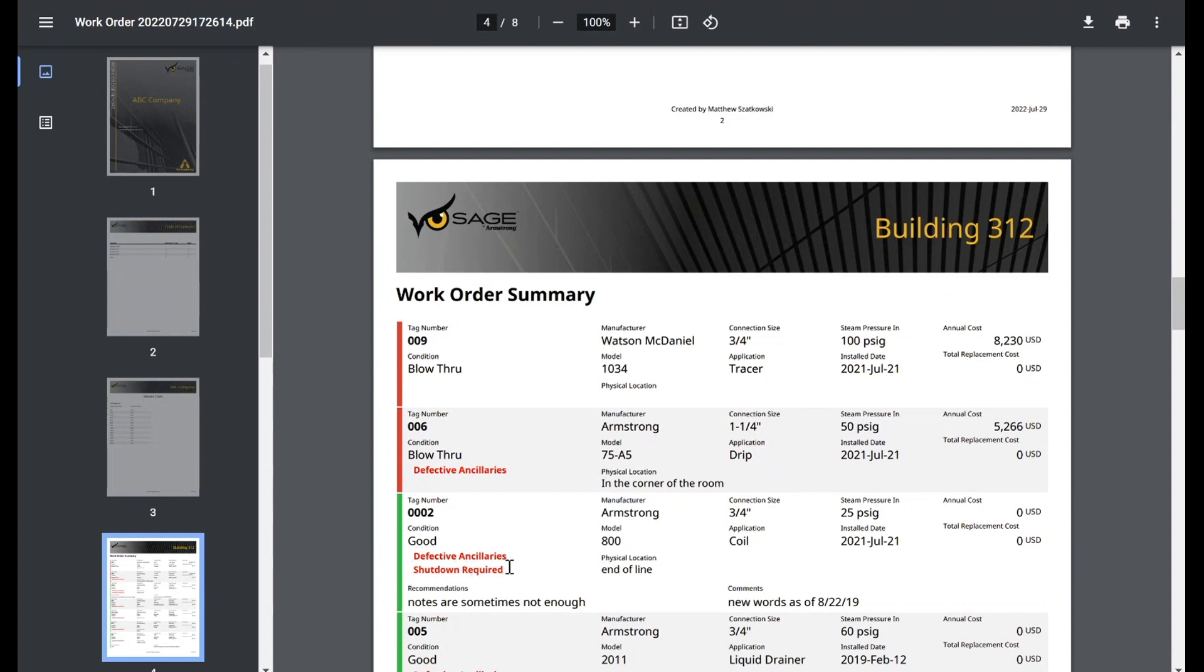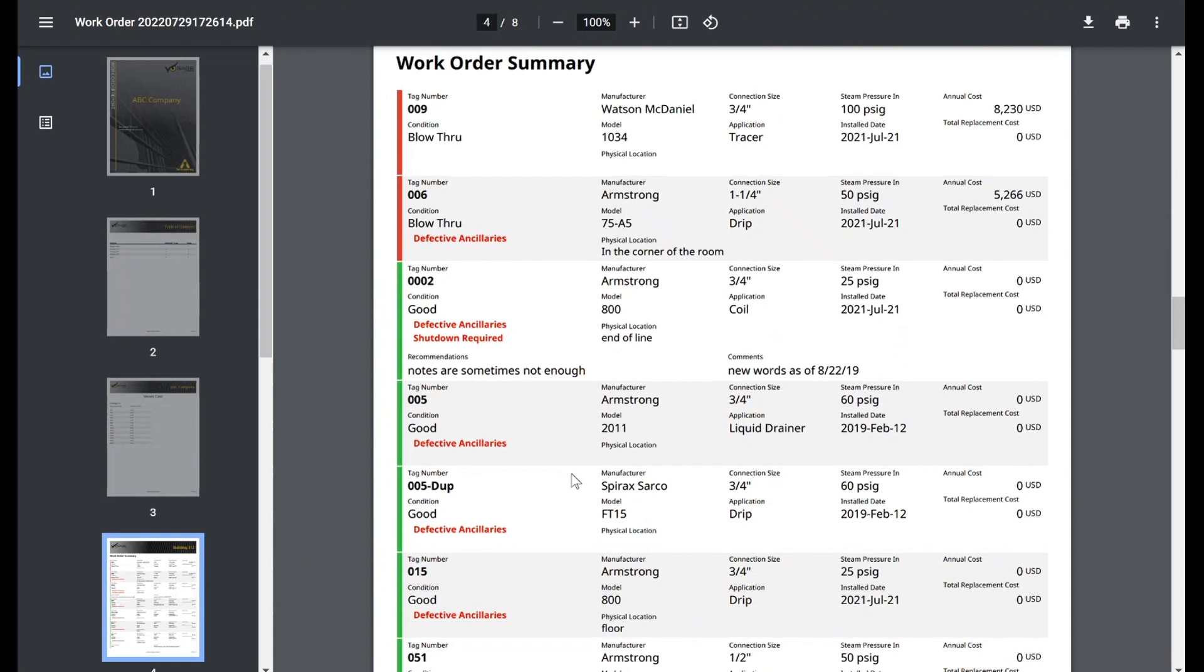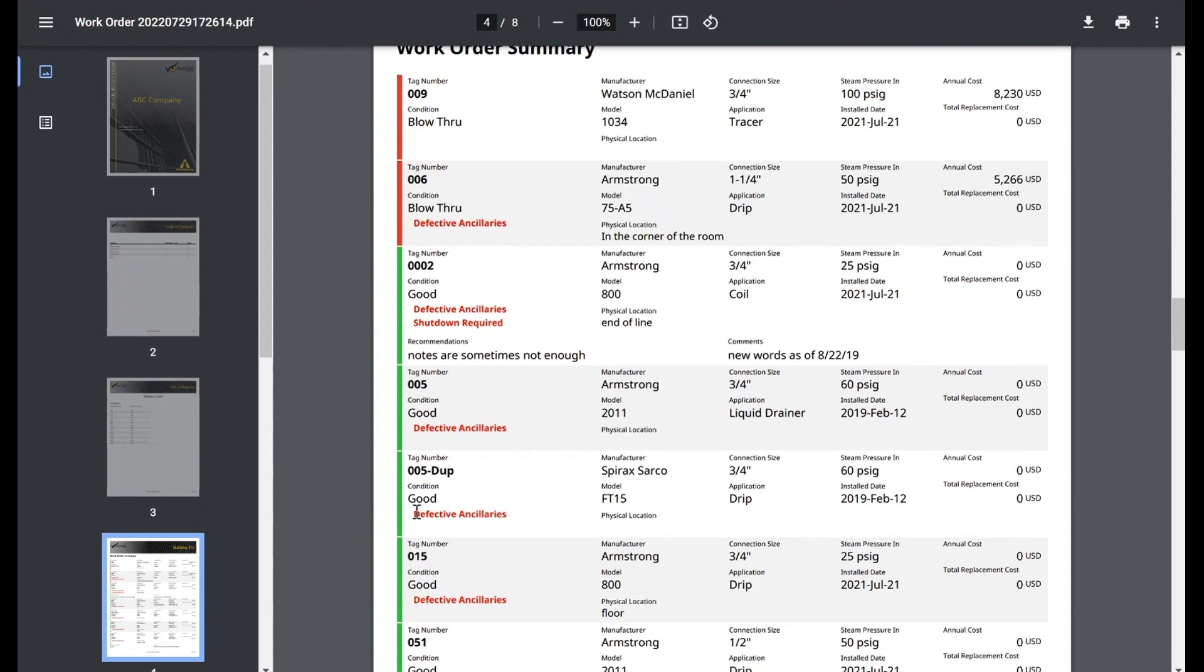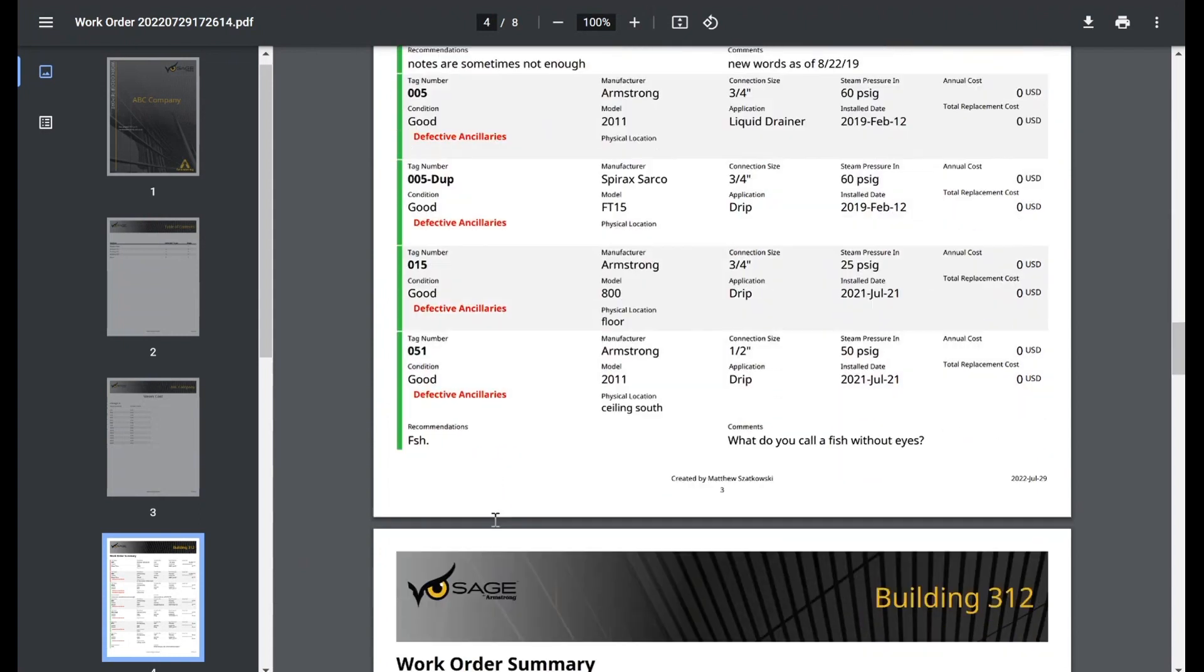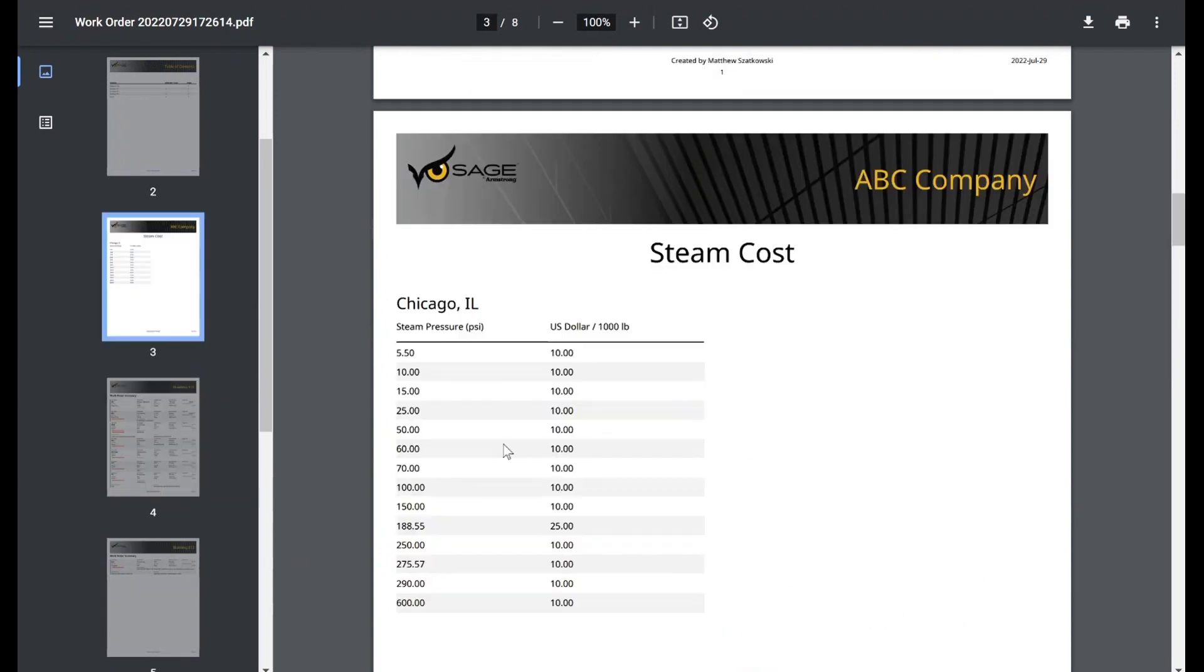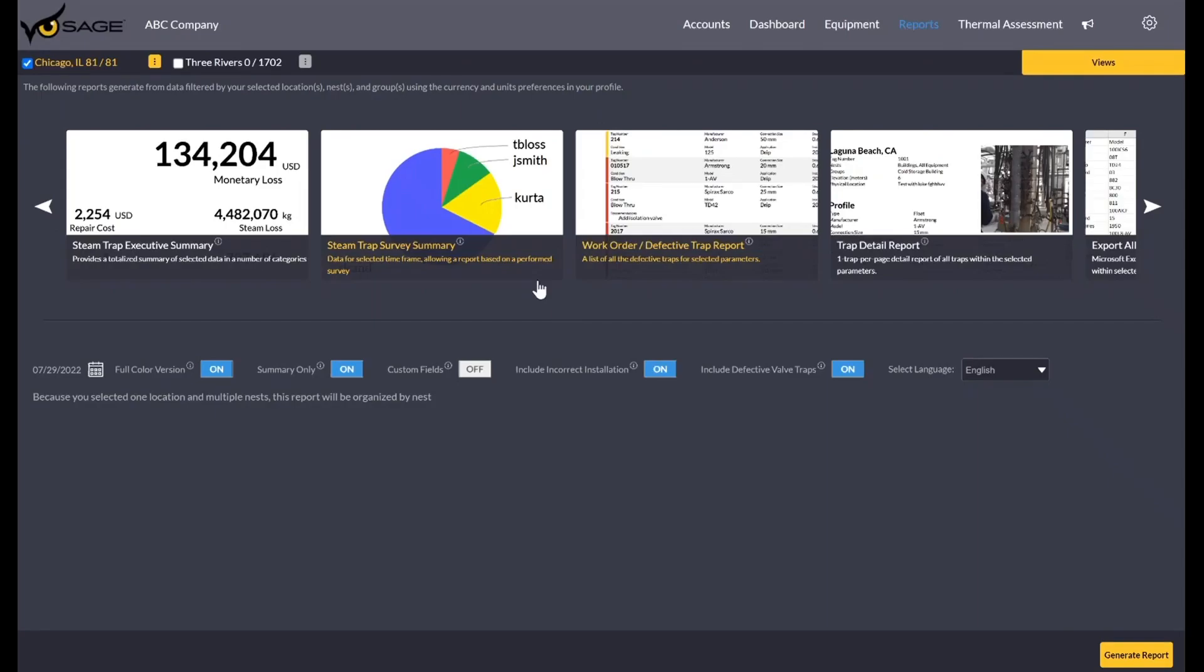And so we can see here, right here we see on tag 002, we have a defective ancillary. It has a shutdown required to tackle it. It's just strips of data for each trap. So again, this is the summarized version. So again, we have 009 blow through. If the physical location is documented or if there's any notes or recommendations, those are included. And you'll see that defective ancillaries is referring to the valves around the steam trap. And so again, that's the summarized version.